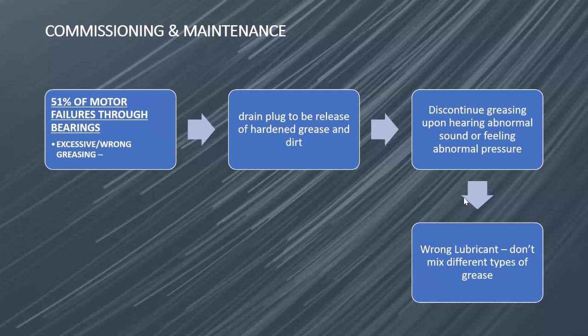When we were looking at the exploded view of the motors, I pointed to the drain plug of a motor. Motors normally have a drain plug so that as you pump in new grease, the spent grease passes through the drain plug out of the motor. But in the case that the plug is blocked by hardened grease, you pump new grease into the motor and the old grease is also there. So you overgrease the motor, and when the motor is overgreased, it causes overheating, and overheating eventually leads to the failure of the motor bearing.